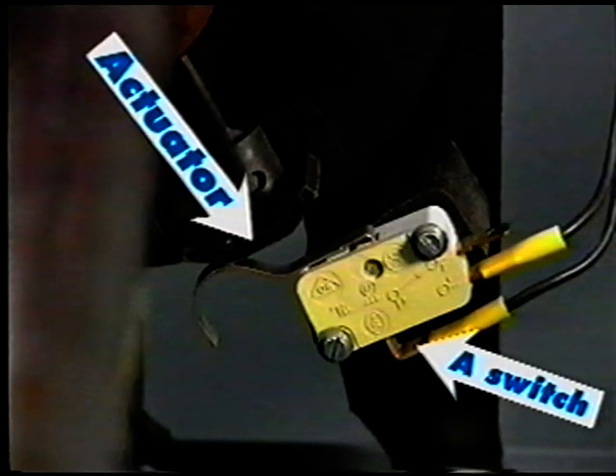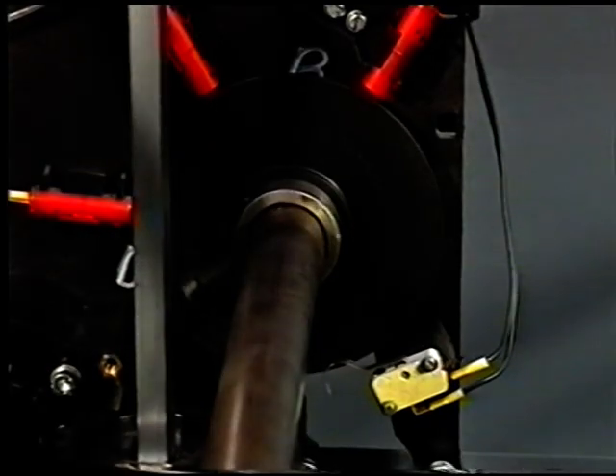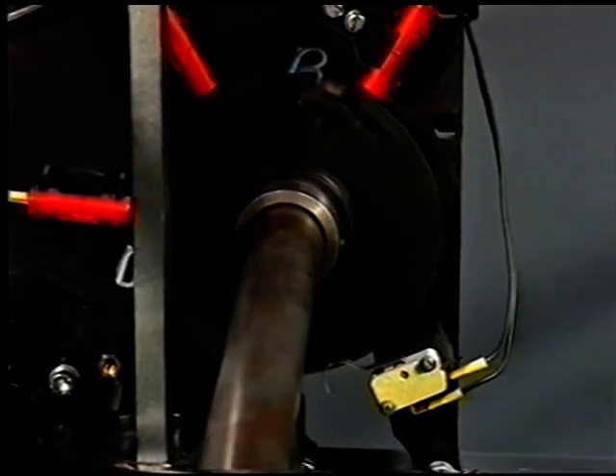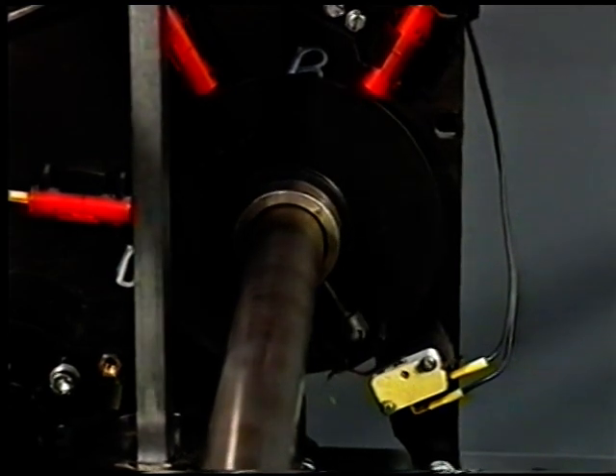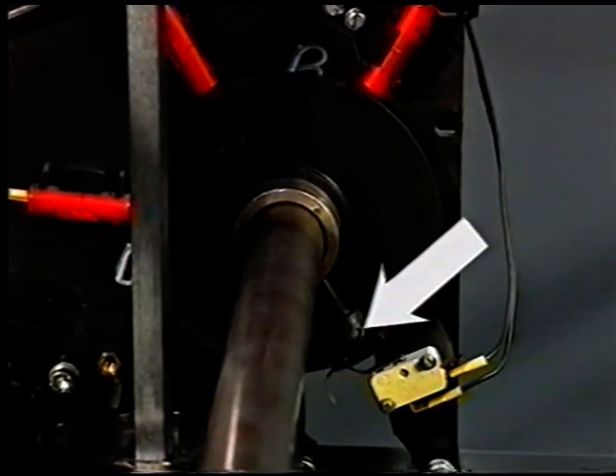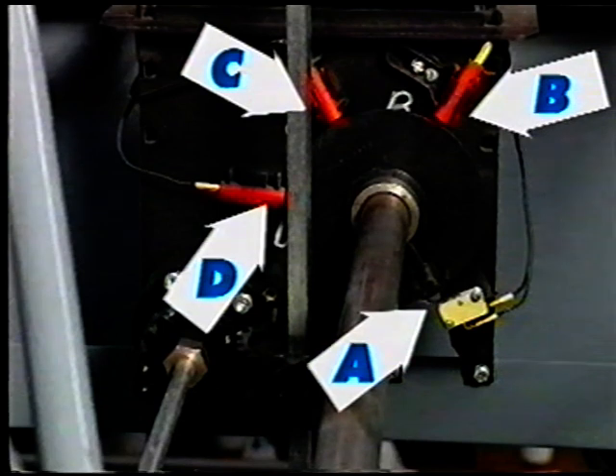The A micro switch is held closed by an actuator when the table is up in the home position. As the table lowers and raises, a small magnet mounted on a cam will close the contacts on the B, C, and D switches. The cam and actuator are designed to activate the switches either clockwise or counterclockwise.